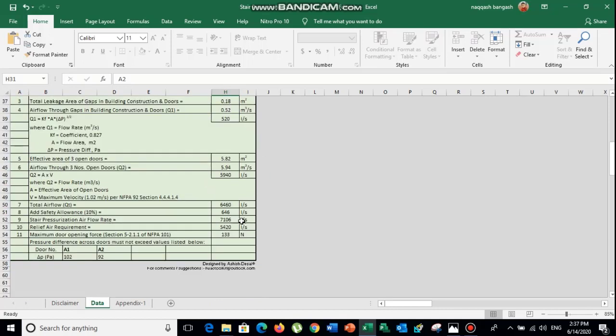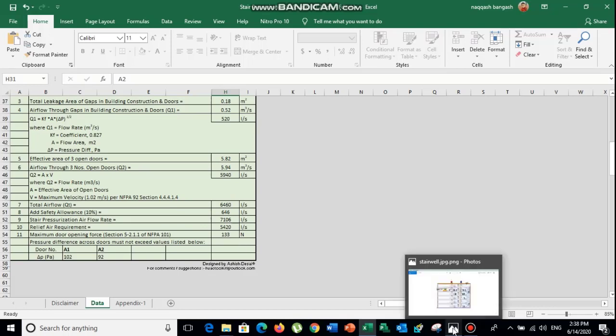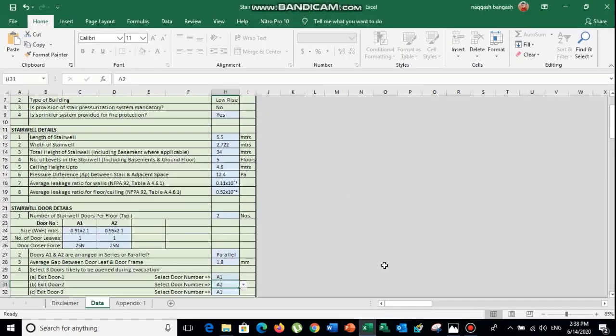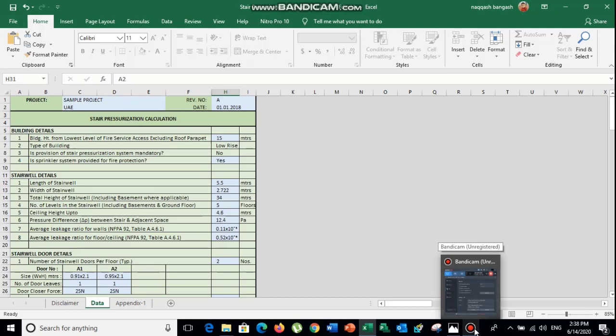Finally, this is the calculated data from the Excel sheet. The total air requirement comes out to 7,106 liters per second for your staircase pressurization system. This airflow will vary according to your building size, and you install a fan with that airflow capacity to pressurize the stairwell. If you have any questions you can ask me, and I will provide this Excel sheet. It is very basic and useful for fresh engineers and designers working on sites. Thank you.